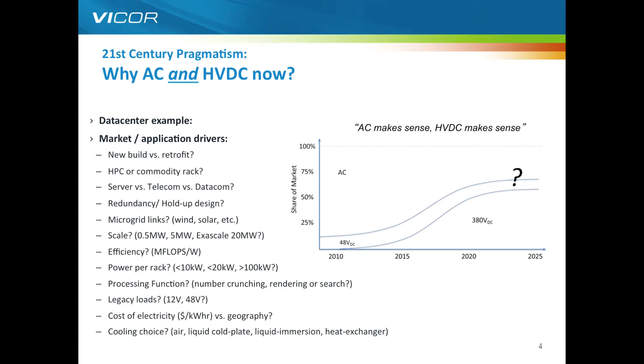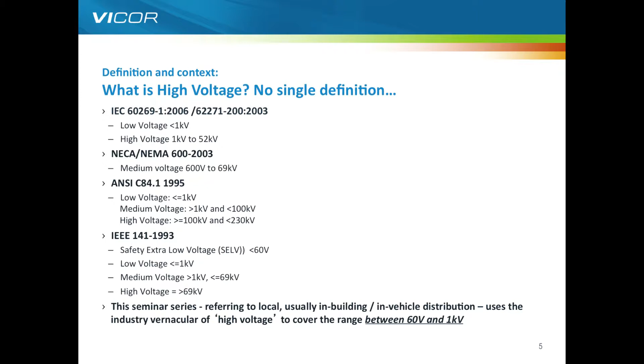When it comes to high voltage, there are various definitions of what we mean, and unfortunately we as an industry, whether it's very high power transmission or low power usage of electricity, don't agree. Between ETSI, ANSI, and IEC, we have different definitions. So pragmatically, for this webinar series, we're going to use high voltage to mean anything between 60 volts and 1 kilovolt. It's an arbitrary vernacular use of the term. I apologize if you're an aficionado of any one of these groups and we're breaking the rules, but high voltage DC is what we're using for 60 volts to 1 kilovolt.